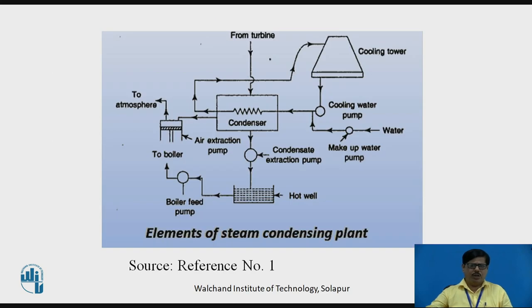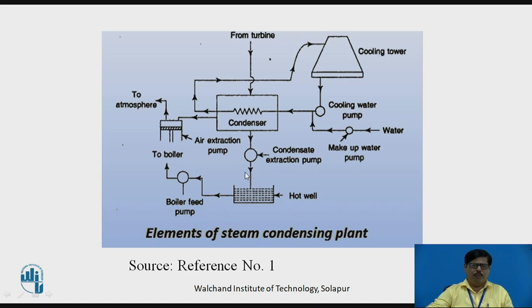The condenser is a closed vessel in which the exhaust steam from the turbine or engine is admitted and condensed into liquid due to removal of latent heat. The steam gives its heat to the cooling water circulated through tubes in the condenser. As the steam gets condensed, the pressure inside the condenser is reduced to below atmospheric pressure — that is, we get a vacuum. This condensate is at a pressure below atmospheric pressure, so it will not come out of the condenser on its own. Therefore, we require an additional pump called the condensate extraction pump.